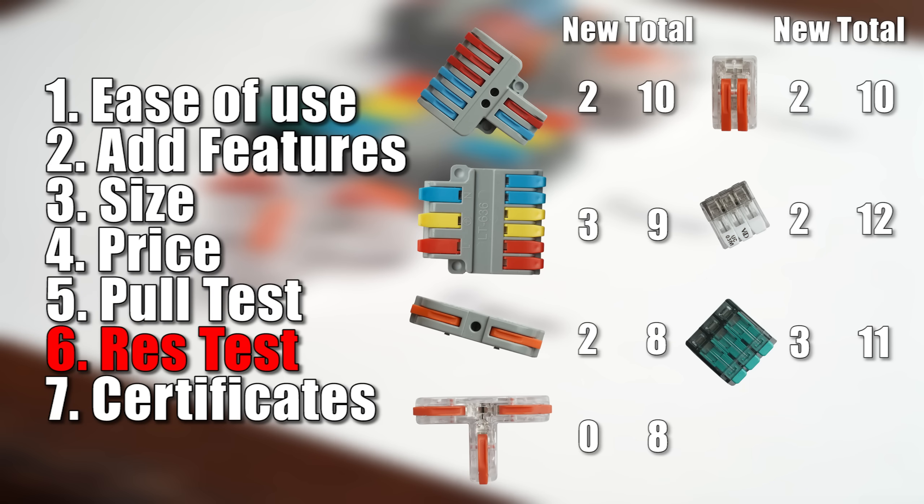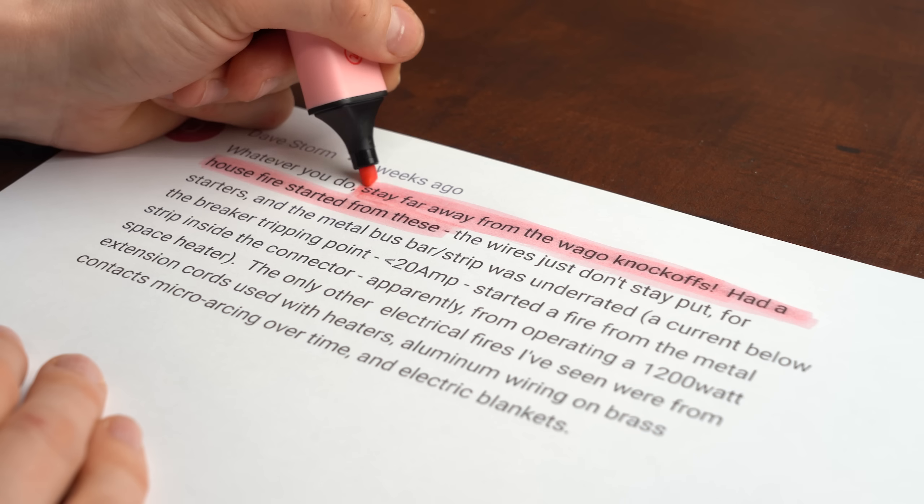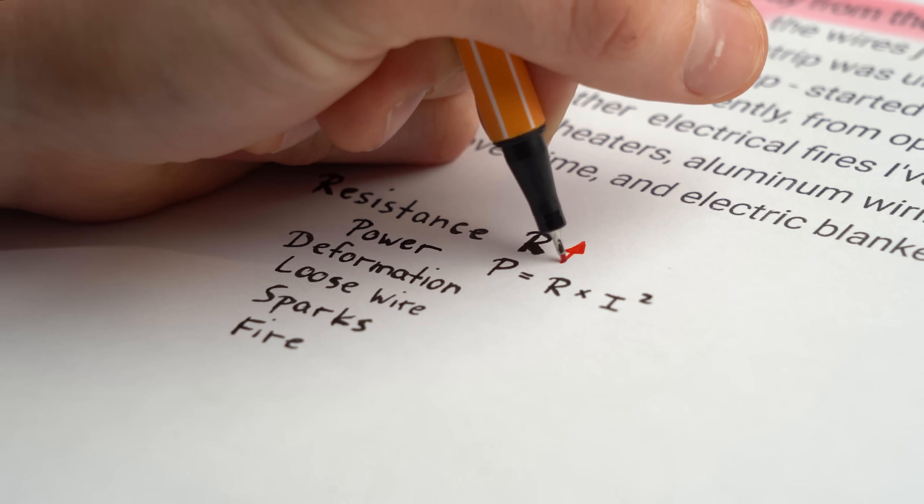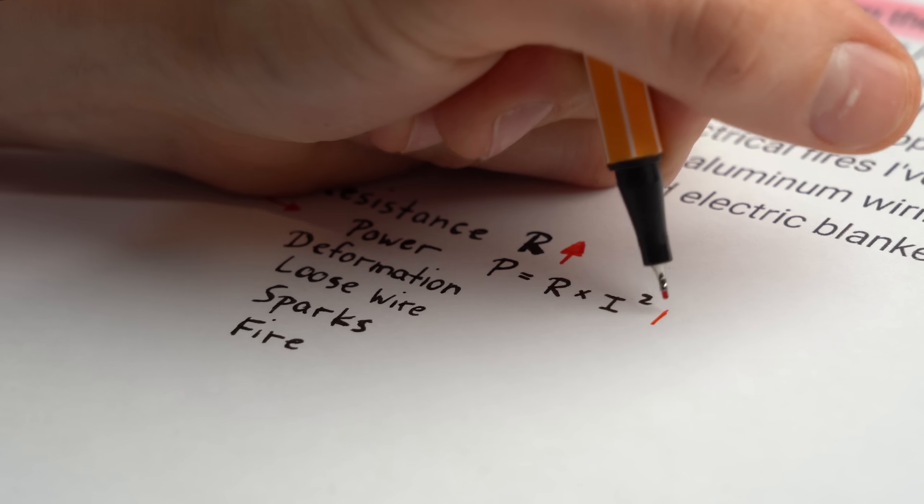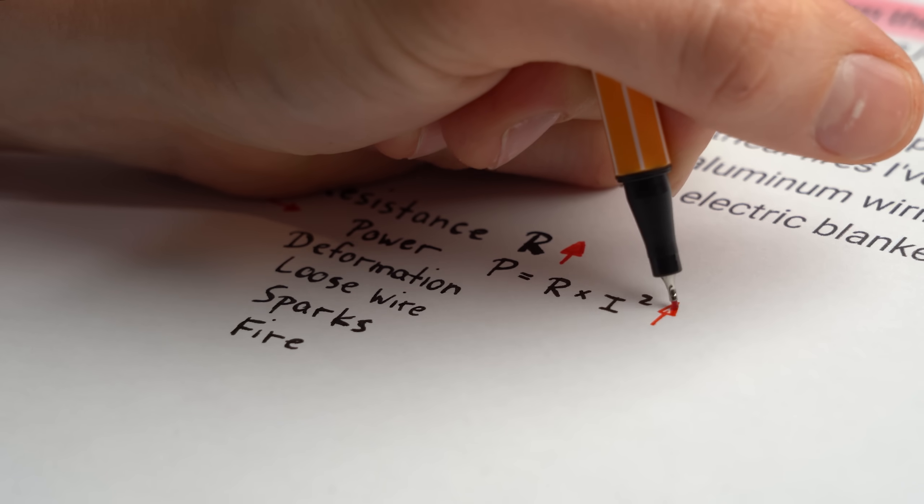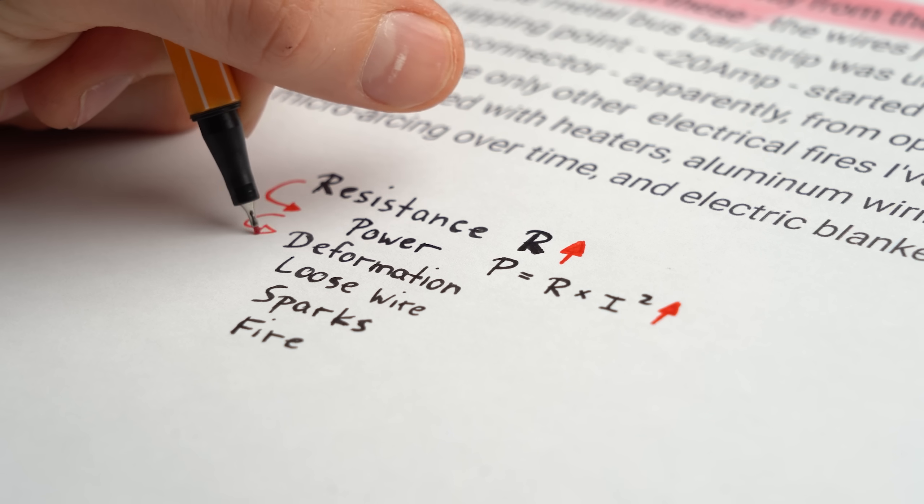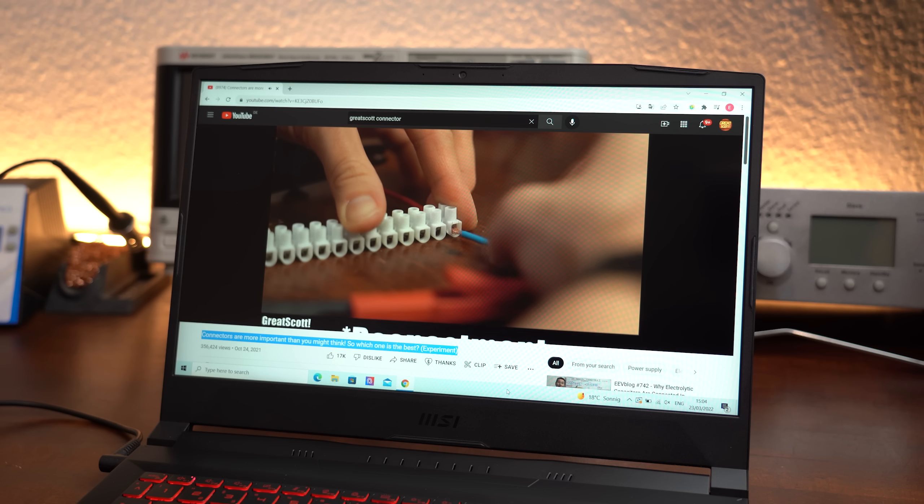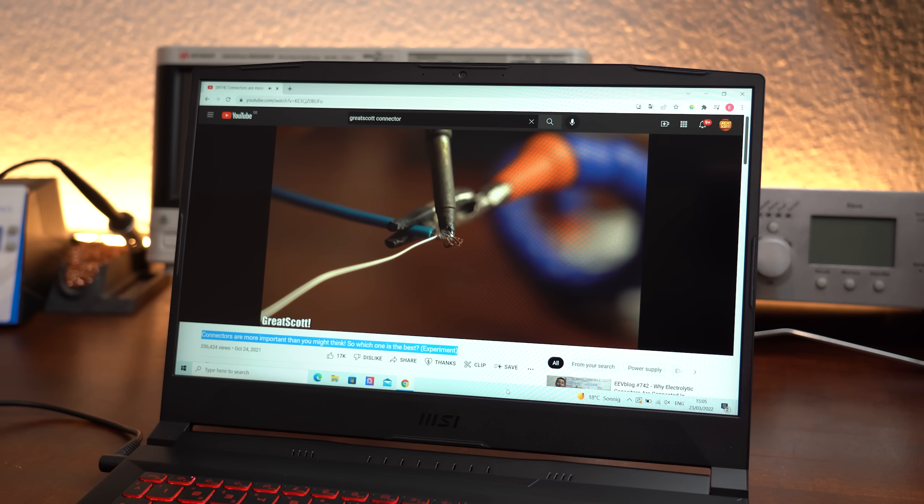So after adding the new points, it was time for the super important resistance test which is related to the comment we began with about starting a fire. You see, the higher the resistance, the bigger power losses get produced inside the connector, which eventually can lead to deformation, a loose wire, sparks, and ultimately a fire. And if that sounds too unrealistic for you, then definitely watch my video about different connector types and wire ferrules.